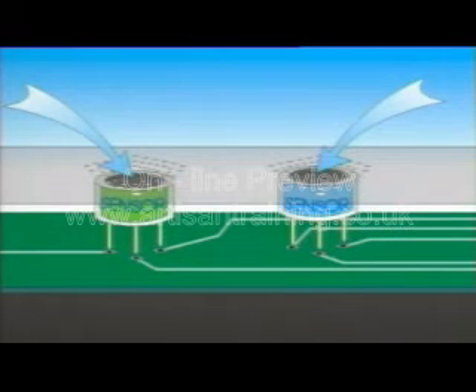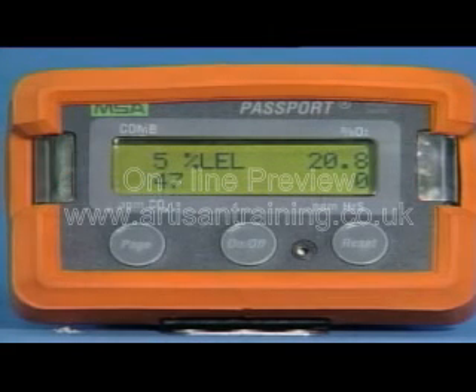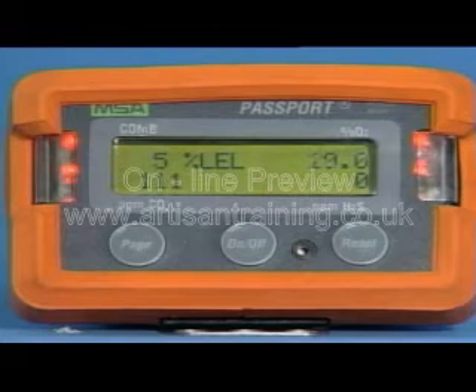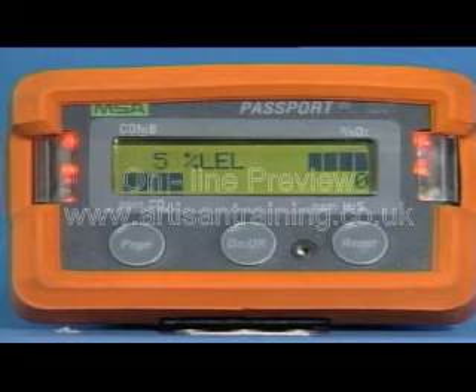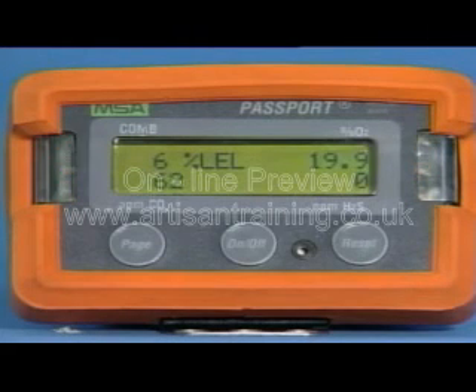Having analyzed the signal, the electronic components then activate a reading on the display screen. If the electronic circuit interprets a reading that matches or exceeds a given set point, then it will activate an alarm signal in the form of an audible sound and with a flashing light. The alarm warns an operator should a dangerous or hazardous atmospheric condition develop.